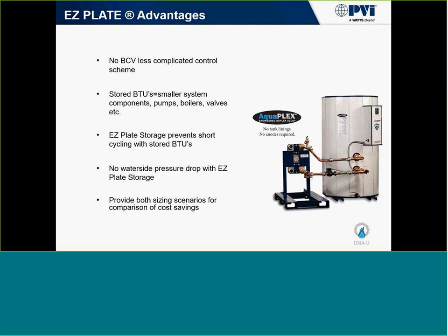And this is really nice if you're using high efficiency boilers, creating that boiler loop. We can scrub a ton of heat off of that and return extremely cold temperatures back to your condensing boilers, which is what they want. So your entire design would function as efficiently as possible, including your hydronic boilers that you might be using.